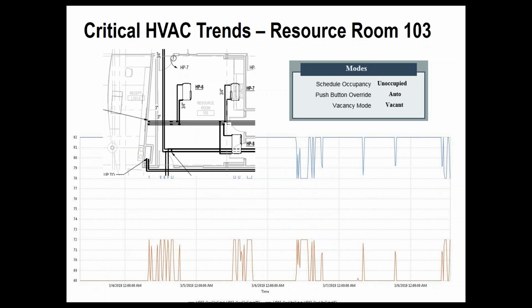This was a simple one, essentially a storage room that's unoccupied all the time, but it would be easy enough for a controls vendor to see that room and just put it on the same occupancy schedule as everything else. So what I wanted to do going through functional testing and verification was to make sure that we had the space pretty much unoccupied all the time, and then occupied when we had an override from the space thermostat or a lighting sensor. And you can see we do pretty well here. We kind of erratically change set points, which is related to the occupancy sensor.